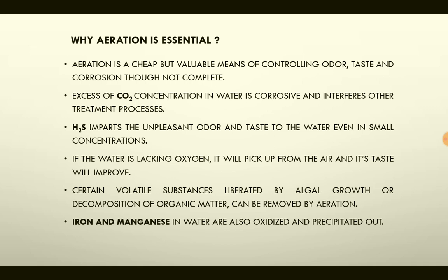Hydrogen sulfide imparts an unpleasant odor and taste to the water even if it is present in small concentrations. If the water is lacking oxygen, it will pick up oxygen from the air during aeration and its taste will improve. Certain volatile substances liberated by algal growth or decomposition of organic matter can also be removed by aeration. Iron and manganese in water are also oxidized and precipitated out during this step.